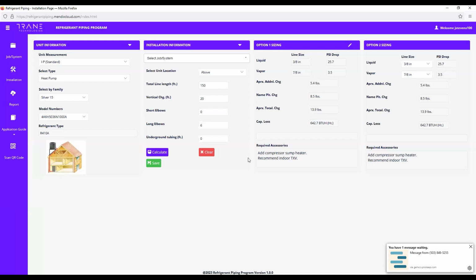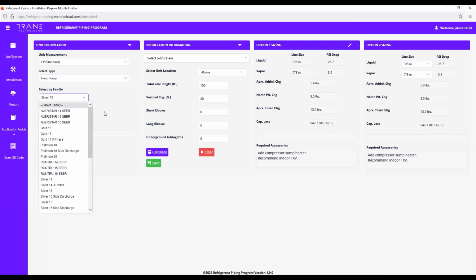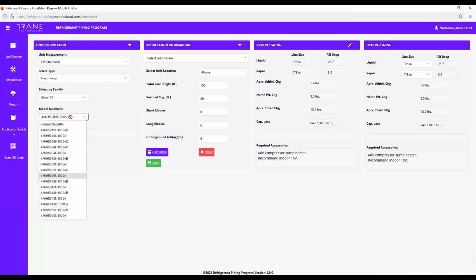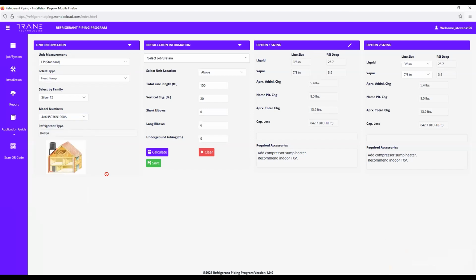Can everybody see that? Okay, sorry about that. Okay, let's start over. Go up here, heat pump. You're going to select your heat pump. Select the family. Select the model number within that family, basically the size you want, or your exact model number of the equipment you're going to put in. Select the location above or below. Total line set length, vertical change, and how many elbows. Then you're going to hit calculate.